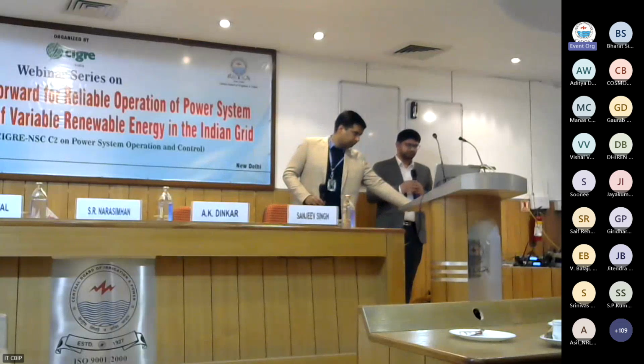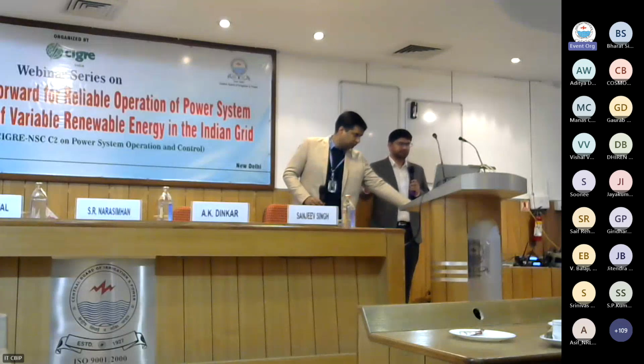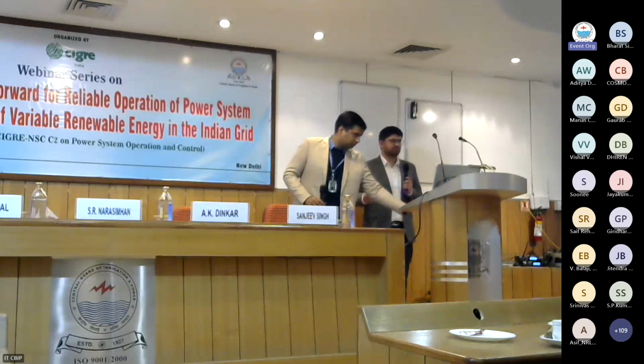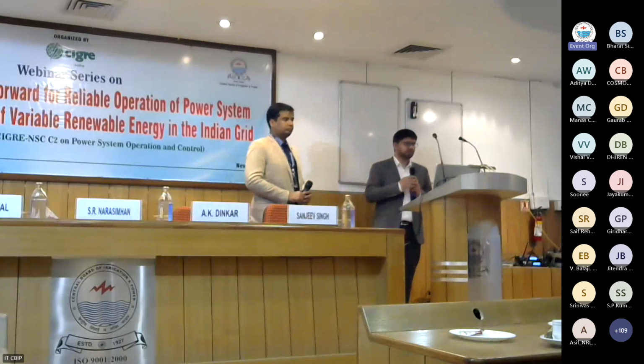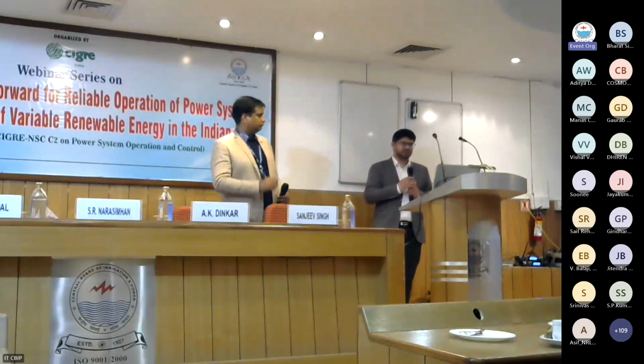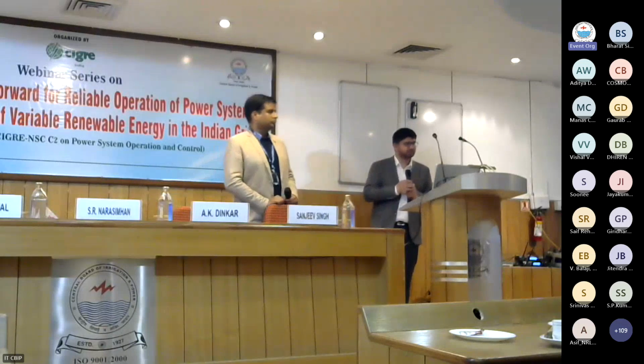K factor also we have tried to modify in some of the cases, especially when the response time is large, and the response is not coming during the fault but after the recovery of voltage. This will lead to high voltages in the grid. So if we reduce the K factor in the plants where the response time is on the higher side, the response will also be lower, and the voltage rise will be within limits. So these are a few changes that we have done, and we have seen the results also.